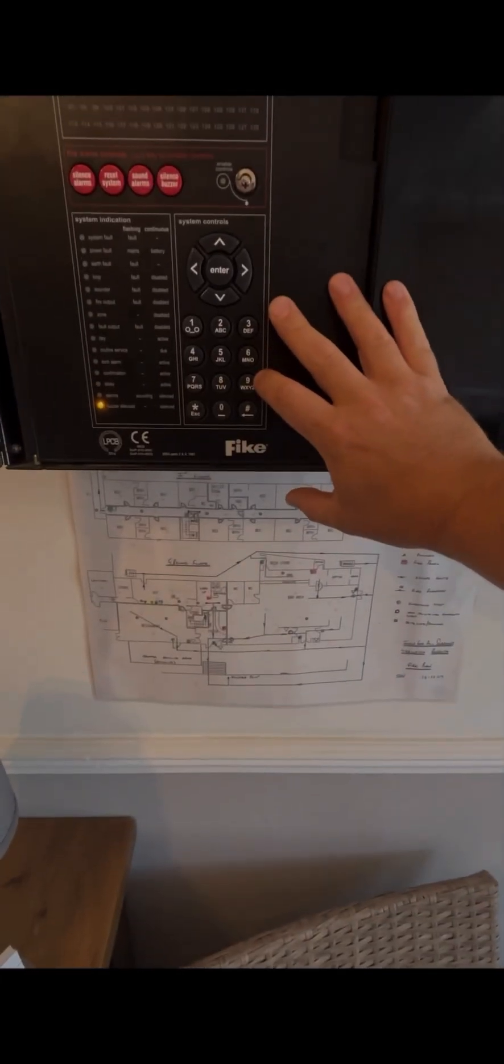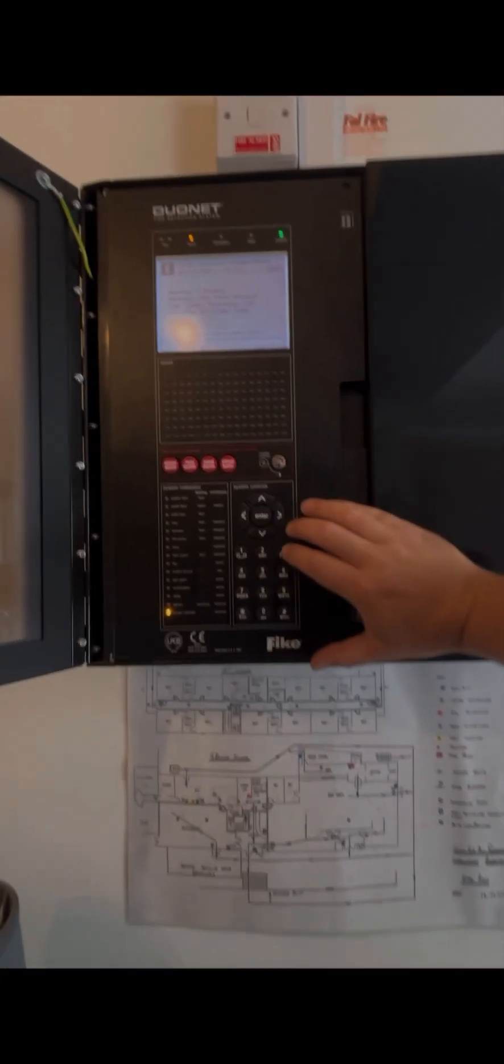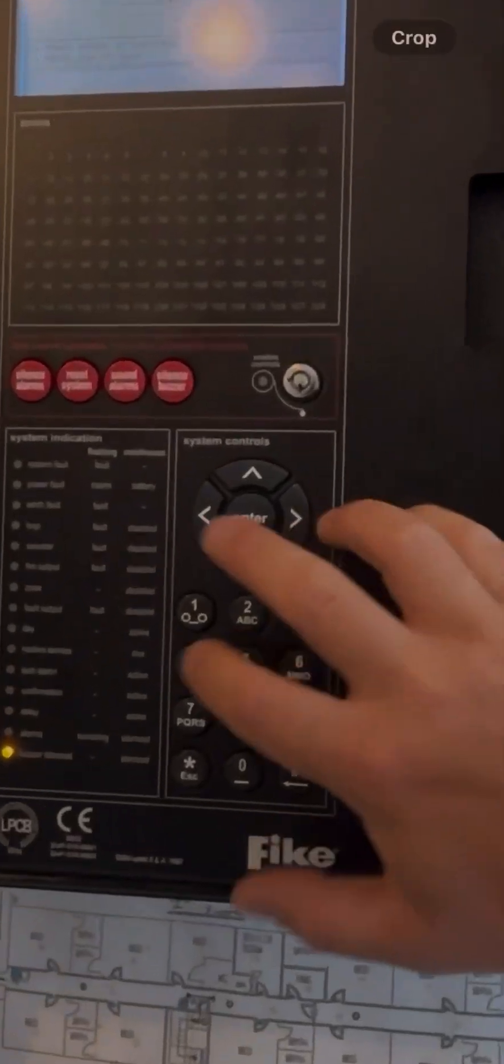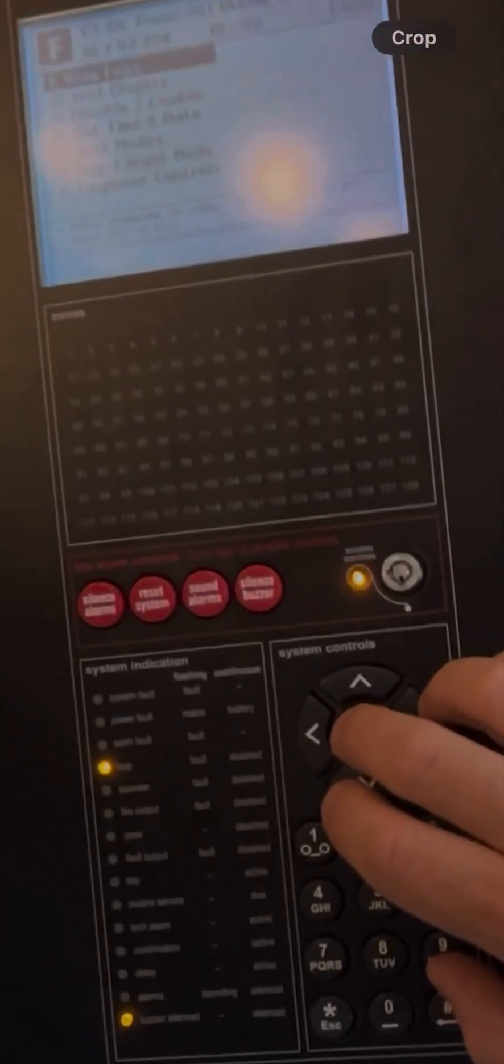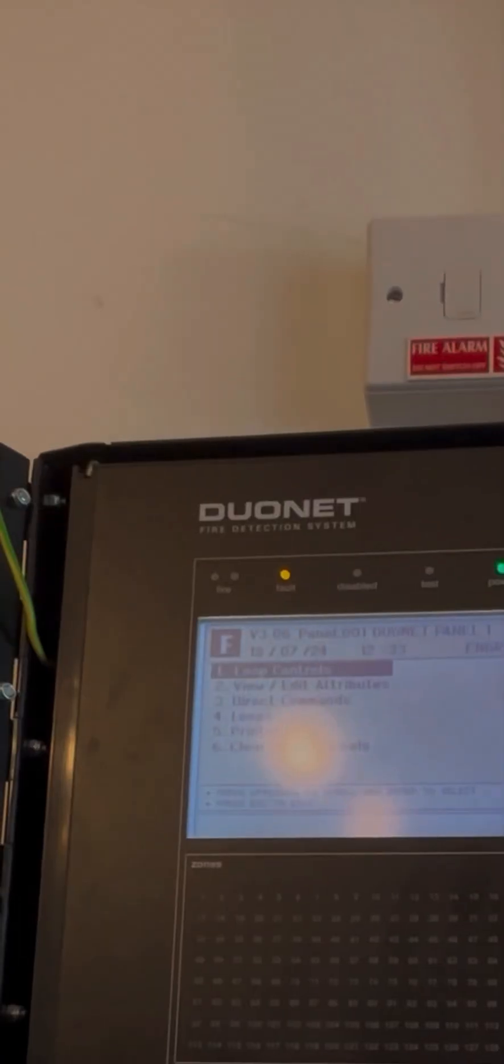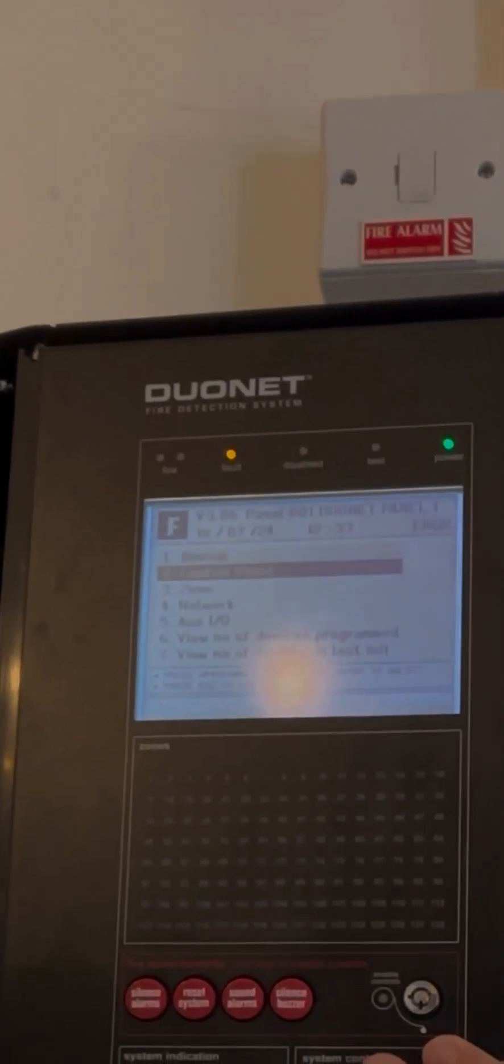First, we need to punch in our engineer code. The default is 3647, which spells out the word 'engineer,' followed by enter. Then scroll down to option 7, Engineer Control. Next, go to View/Edit Attributes and scroll all the way down to the bottom to number 7 to view the number of devices last initialized.